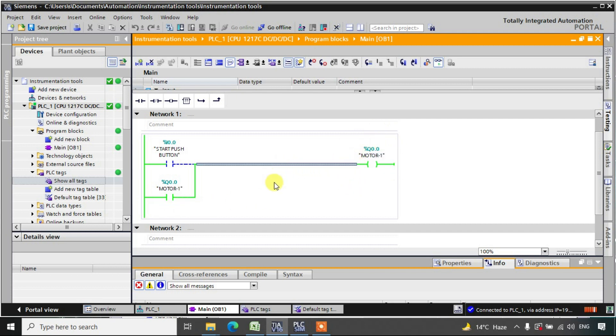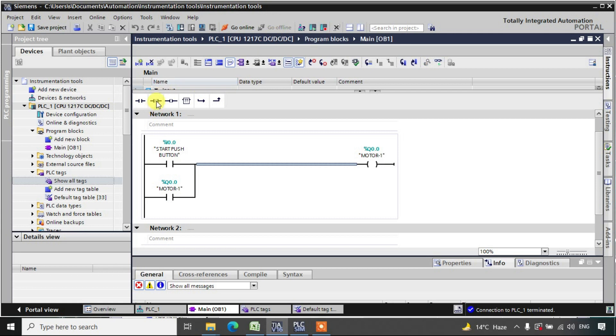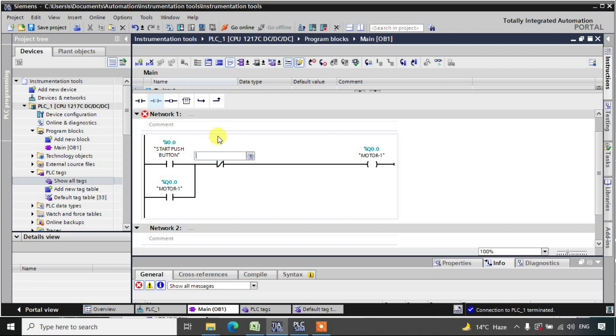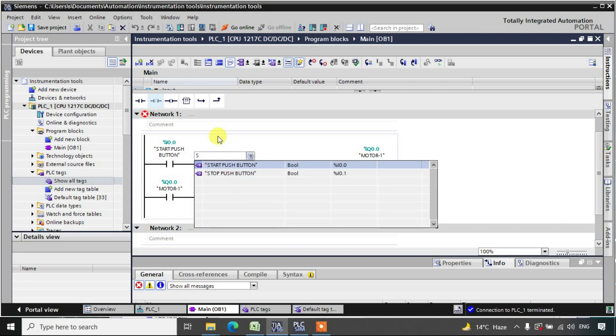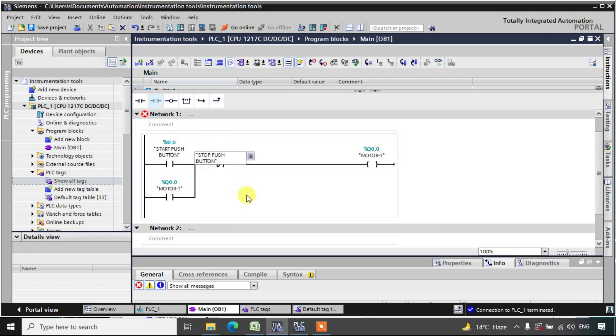Now we need to turn off this motor — we need a breaking circuit. To use a breaking circuit, I will go offline again and add one NC contact in series with the output. I will give it the address of the stop button, I0.1. Now I will download it again.